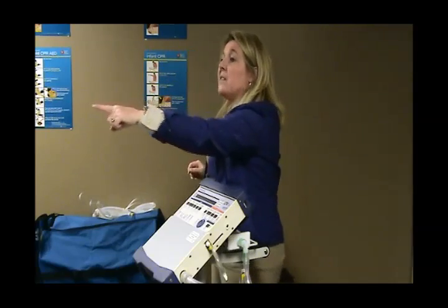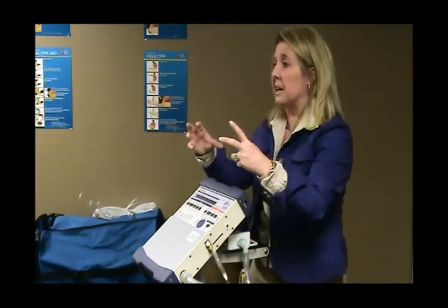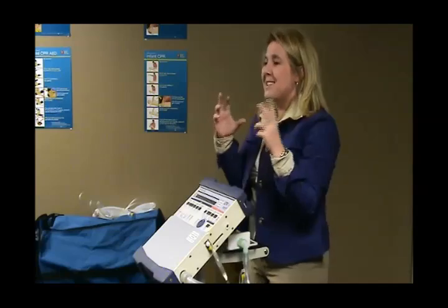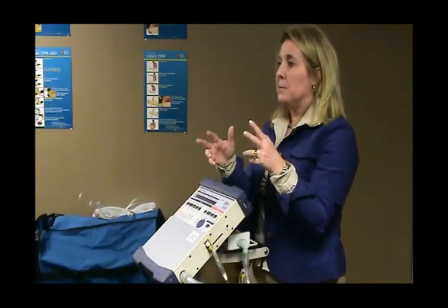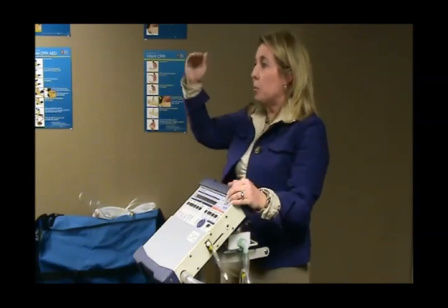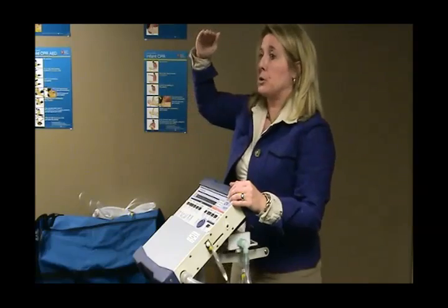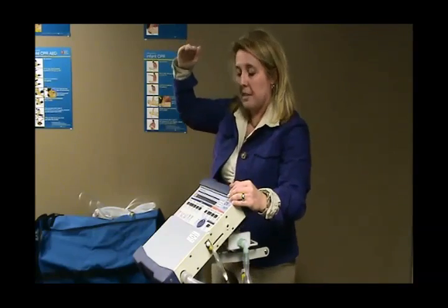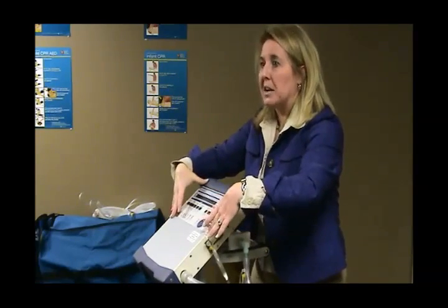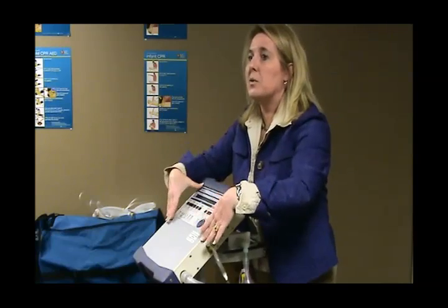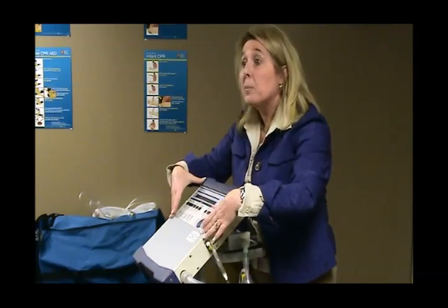Okay? So with that ventilator, with our older style ventilators, which are called not PEEP compensated, when you set the pressure, it is the maximum pressure the patient will get on a pressure breath. On our new style ventilators, the 1100 and the 1150, they are PEEP compensated.